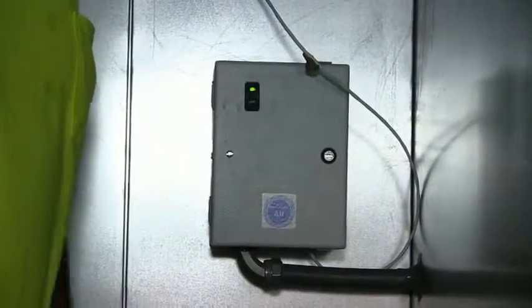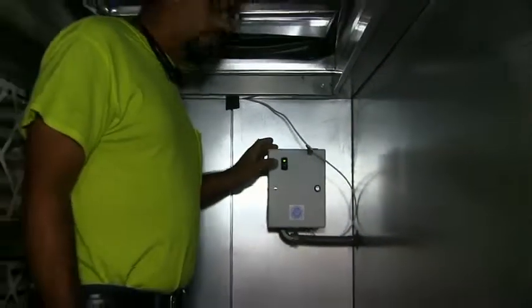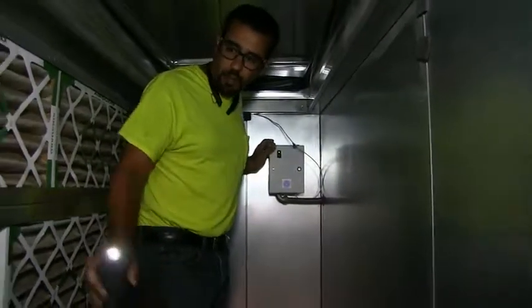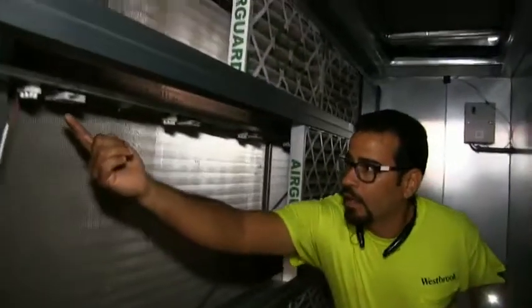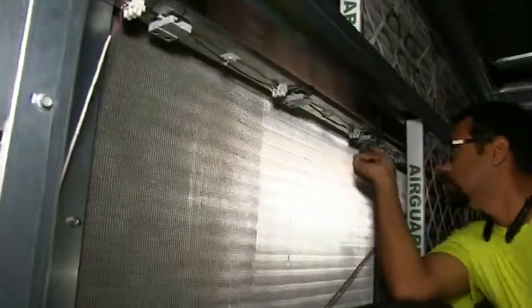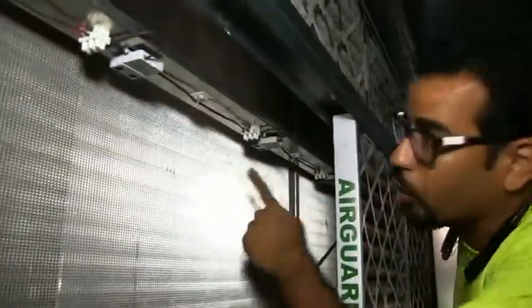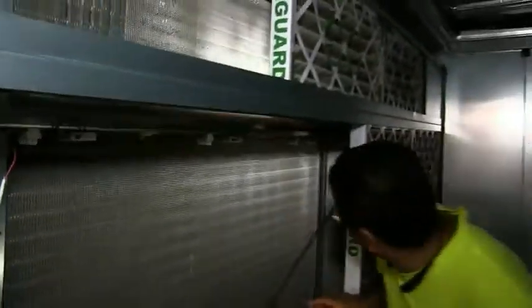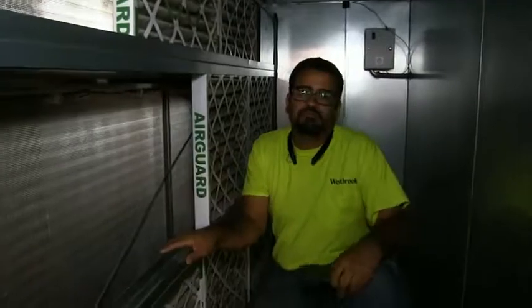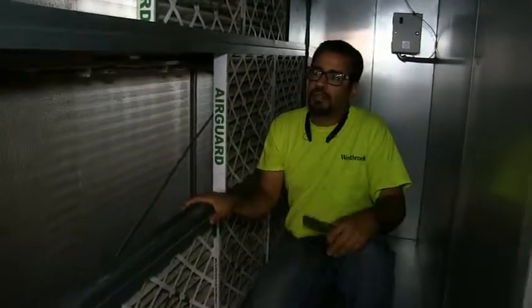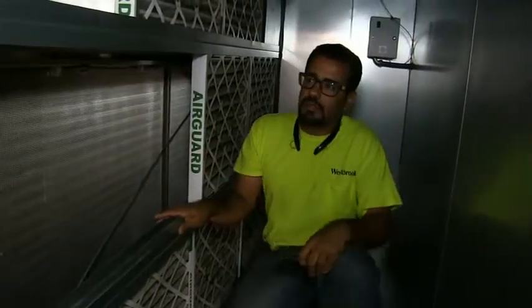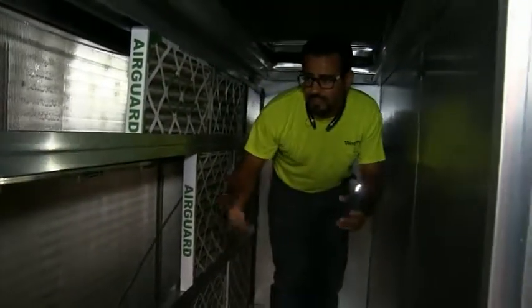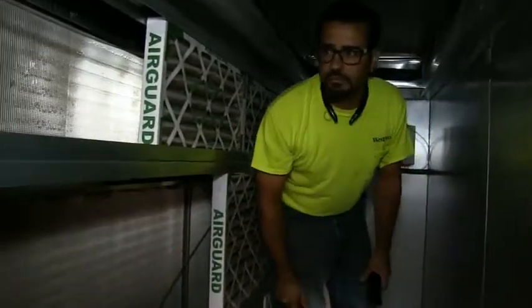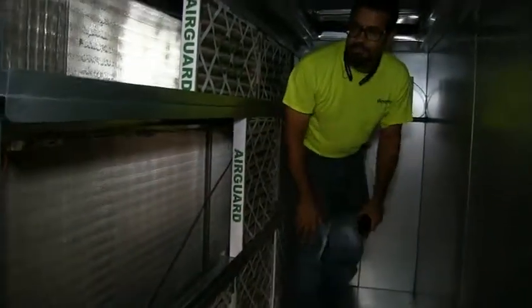Free maintenance. The only thing you can do, as I said, is every 6 months or every time you clean the coil, turn it off over here and then vacuum the needles. It's needles all the way along the bar. That's the only maintenance required. This equipment basically never fails. I've never seen one damaged in the last 10 years, so it's really good equipment. Free maintenance, no parts needed, and that's basically what it is.